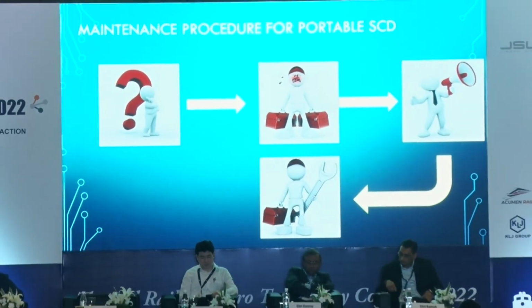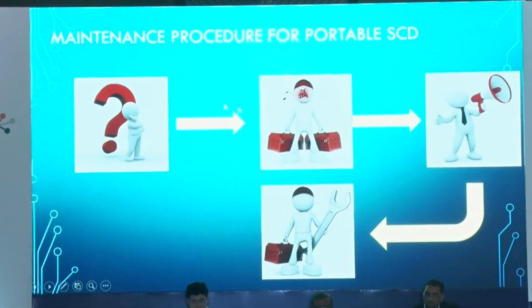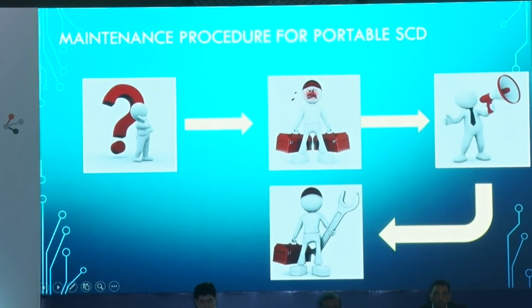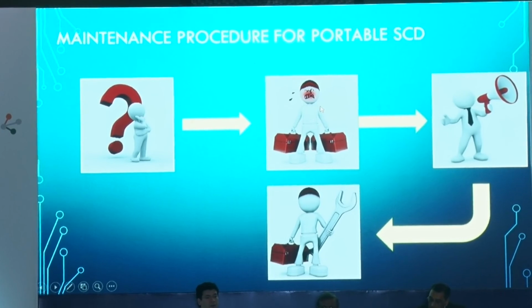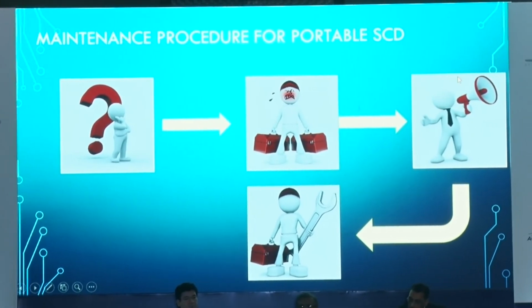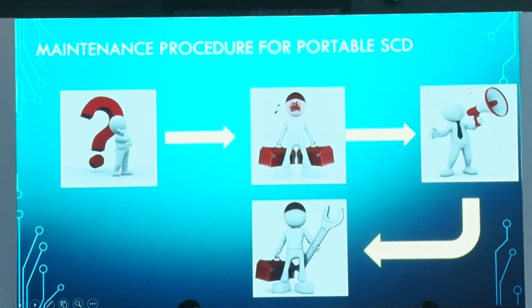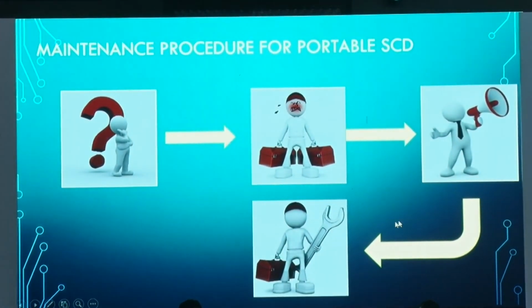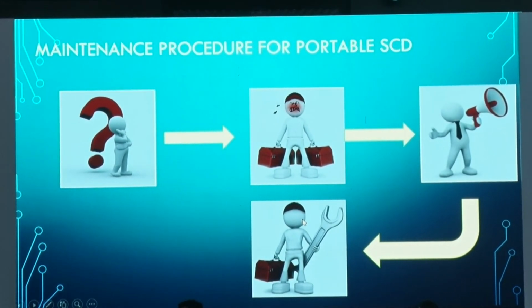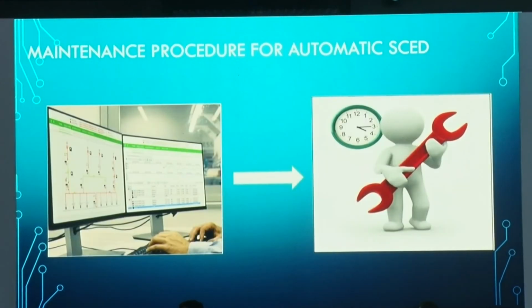Whenever we are using a portable SCD for maintenance, the process is the staff has to take the permit to work. After taking permit to work, he has to check where the portable SCD is kept. Then they have to carry this portable SCD all the way along with all the tools, spares to the site where the maintenance is to be done, which is typically around 500 to 600 meters from the station. Then there they need to check whether the third rail or running rail is off or not through some voltage detector also. Then after that only they can start the maintenance. In case of automatic short circuit and earthing device, they just need to obtain the permit to work, tell the SCADA operator to do a few clicks, and after the few clicks, they are ready to do the maintenance.